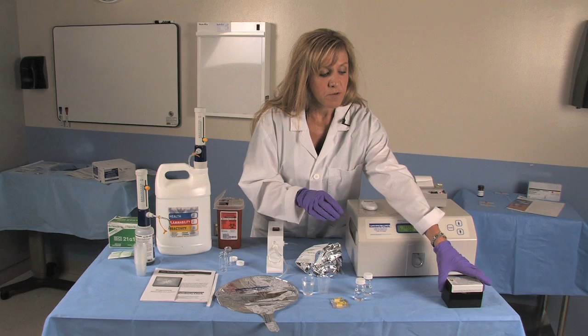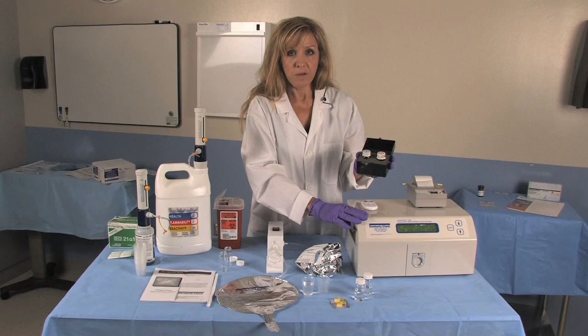The standard set label for the carbon 14 standard will have a DPM value listed. That is the new default value. So every time a new standard set is ordered, this machine default value must be changed. Again, that's page 9 and 10 of the owner's manual.